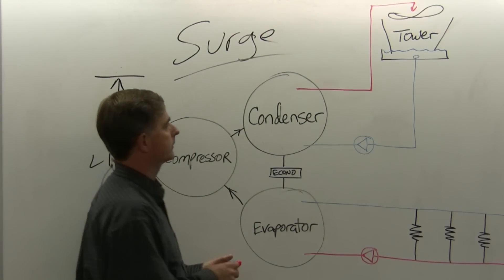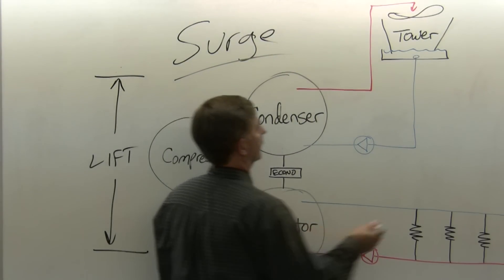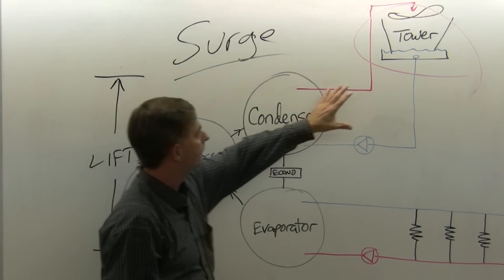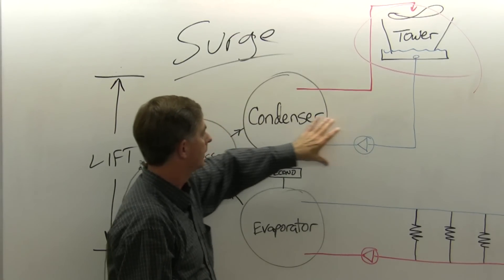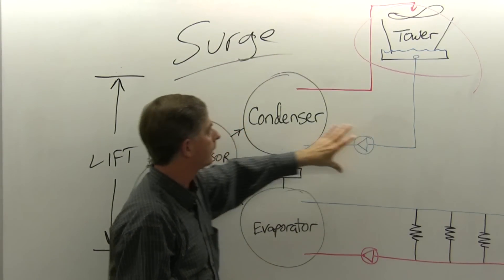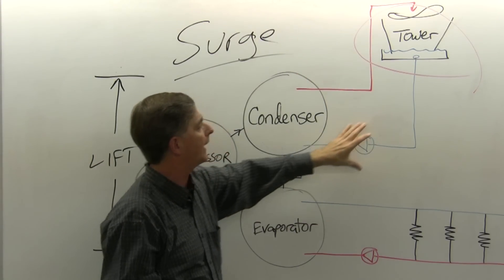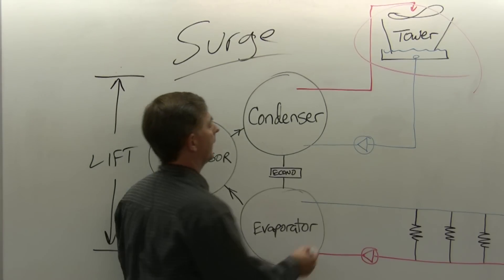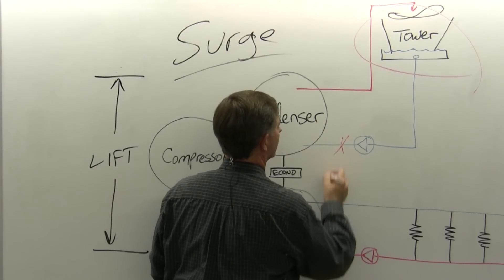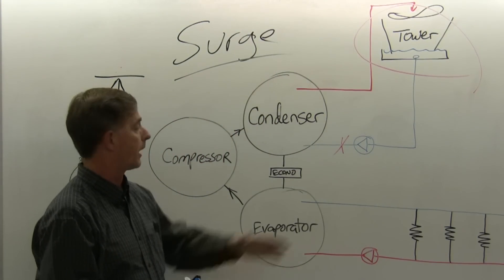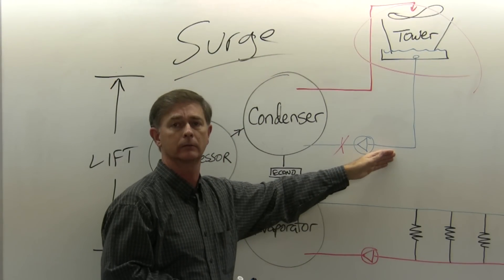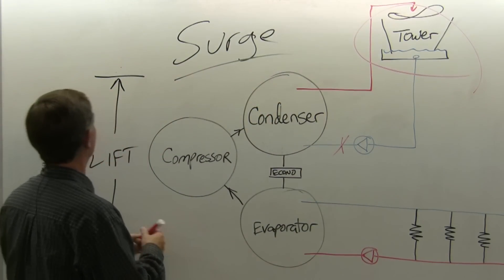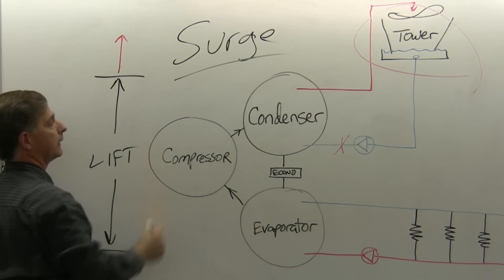One of the biggest causes of surge is right here with the cooling tower. If we have our water going through the tower and we have a reduction in flow, possibly a stopped up strainer, then the pressure in this condenser will rise and lead to surge.